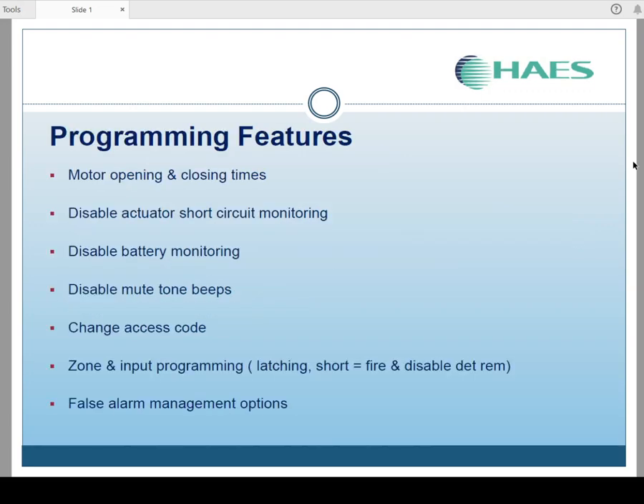So the programming features for this panel, you've got the motor opening and close times that you can set individually. You've got the disable actuator short circuit monitoring. This is useful if you've got a motor that falls below the 10 ohms. I have to be slightly careful here, so it will allow the use of the older motors, but they must still be within the current range of the panel, and they must be no lower than 1 ohm short, otherwise it will damage the panel output.